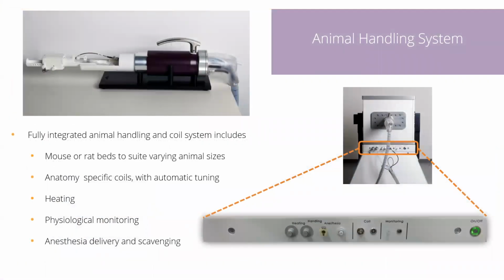The animal handling system is quite simple. This pulls out of the magnet itself. The imaging coil, if it's a body coil, would slide over top of the animal, and I'll show you a video of this in a minute. And there is integrated heating within the bottom of the animal coil, or bottom of the animal handling bed. There's anesthesia, traditionally using isoflurane, both with anesthesia delivery as well as gas exhaust, so that there's not an excess amount of anesthesia building up in the imaging chamber.